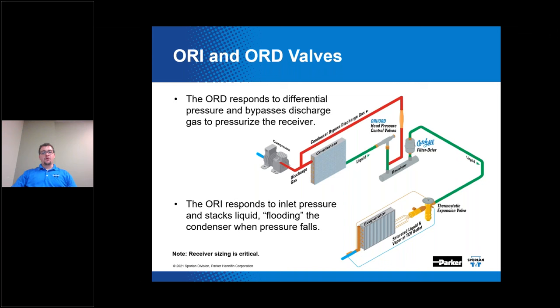To avoid erratic receiver pressure, you need a separate ORD valve to control that receiver pressure. The ORD gets its name from its operation — it's Opening on Rise of Differential Pressure. It pressurizes the receiver with discharge gas, maintaining a constant receiver/condenser pressure for stable TEV operation during low ambient. The ORD should be fully closed during high ambient conditions and only bypass discharge gas during low ambient temps.